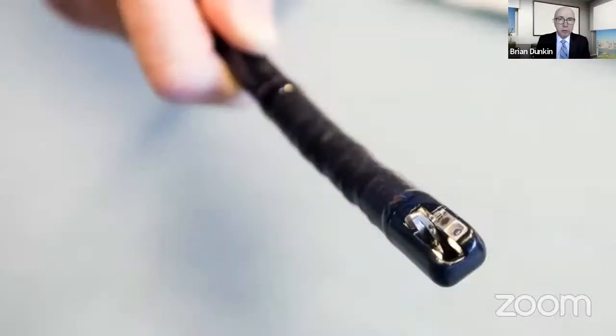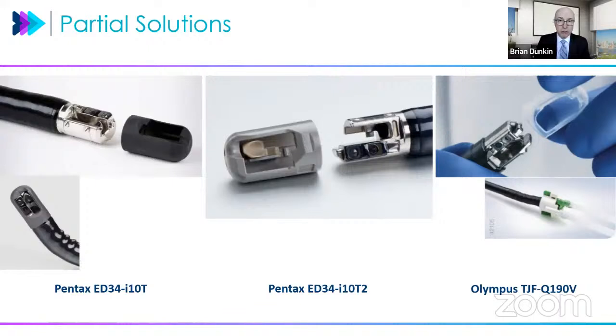The other thing that became clear was more of the root cause problem of what was happening here. In the beginning, this problem of duodenoscope-acquired infections was felt to be due to the tip of the endoscope. Now, this logically makes sense. That is the most complex part of the duodenoscope, as we know. Lots of moving parts there and places where bioburden and bacteria can hide and be difficult to clean. And this led manufacturers of reusable duodenoscope technology to change their tips in order to try to mitigate this problem with different portions that were removable and different cleaning applications applied to the tip of the endoscope. And some of these are commercially available now.